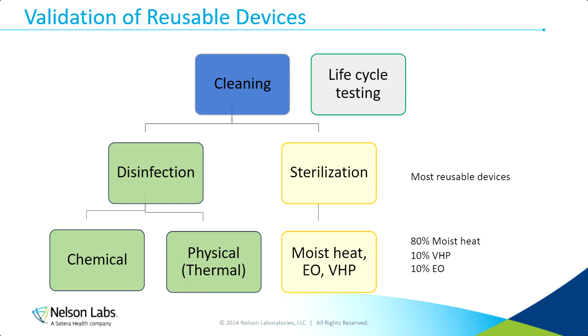Most reusable devices we see will go through a sterilization procedure, and then within that, most will go through a moist heat sterilization procedure. And then ethylene oxide and VHP are optional alternative methods if that particular device may not be able to withstand the conditions of a moist heat or steam sterilization.